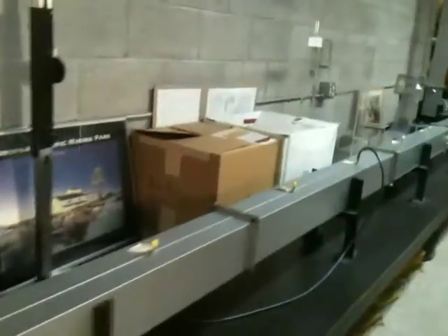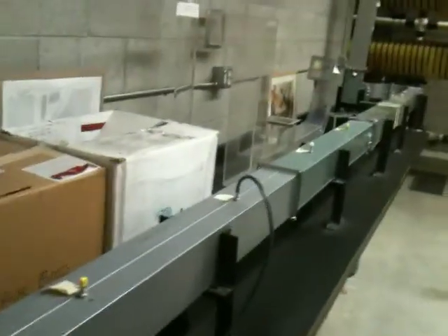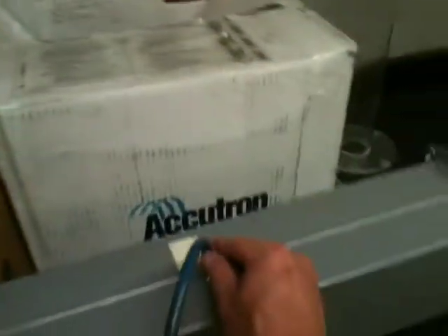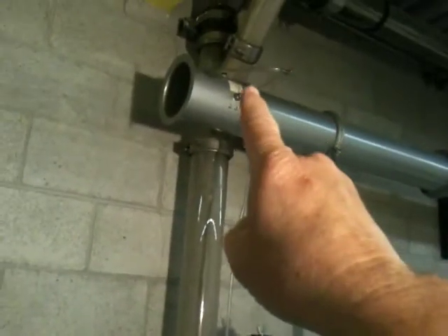This is the frame where we're going to put in the flow restrictions. And then what we're looking at for P, we're looking at the change in static pressure throughout the rest of the airway. So we're a little bit ways down from where we put in the restrictions to let the flow equilibrate in this region. So this pressure tap is connected to the positive side of our manometer. Air flows down to the end, up above, back to the discharge, and we take another pressure reading at the discharge. Remember, air always flows from a region of high pressure to low pressure. So that's the negative side of the manometer, and that's the positive side.